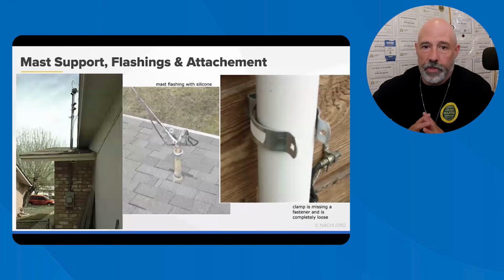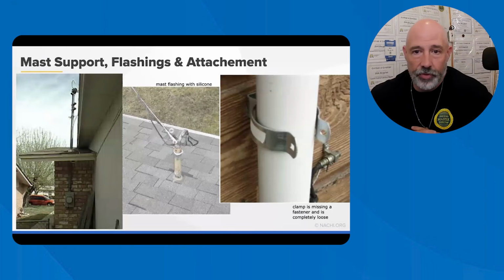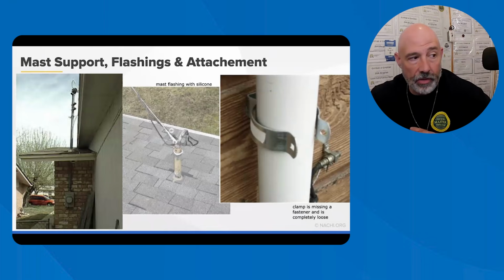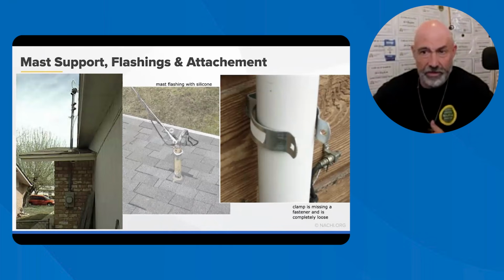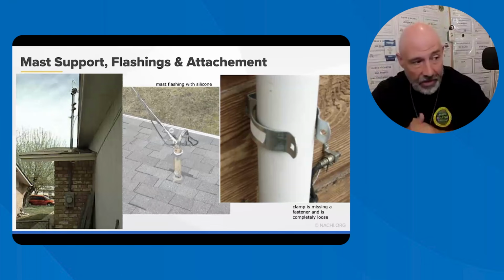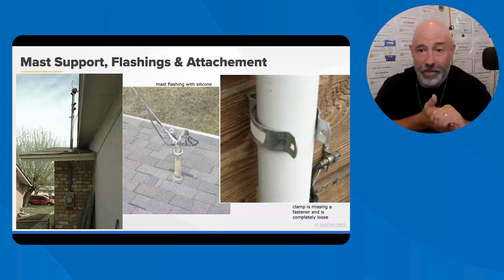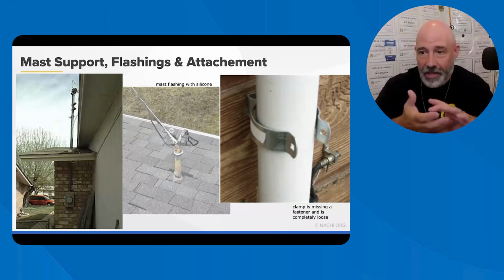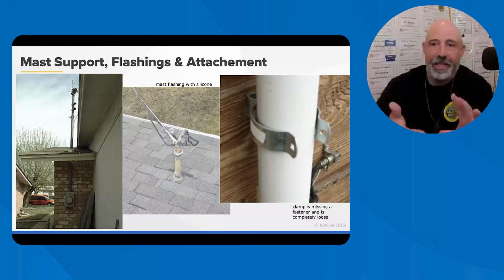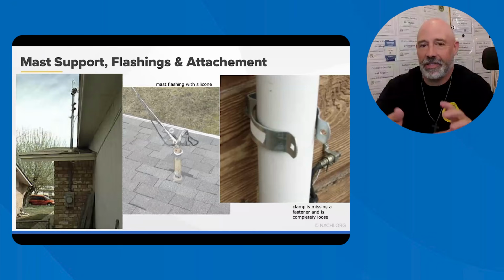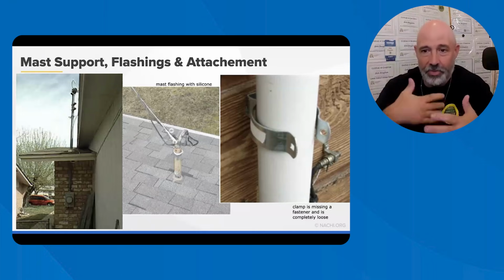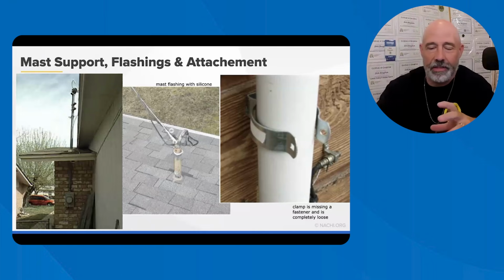Service mast for supporting, you want to make sure that you are looking at the service drop and the overhead service conductor. The mast should be at least 3 feet above the roof line. It should be well supported. The weight of the cable assembly, consider it, make sure that you're keeping an eye on this. If it's leaning too much, if cables are broken, it's common to see telephone cables and TV cables, satellite dishes, clotheslines, things like that. The overhead service mast must not support such things. So you really need to look at this and say, yeah, that's not really designed for that.